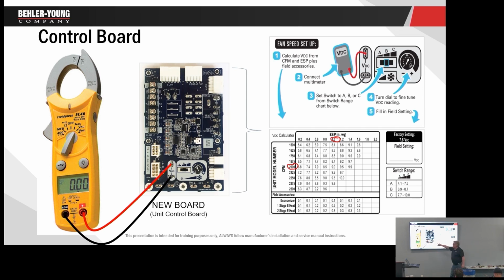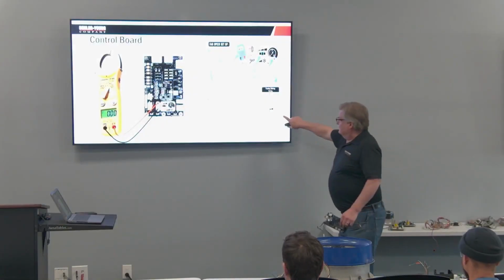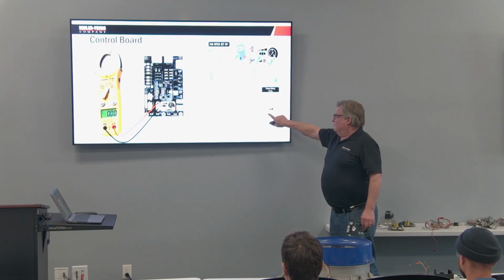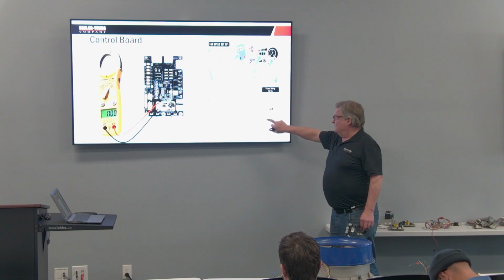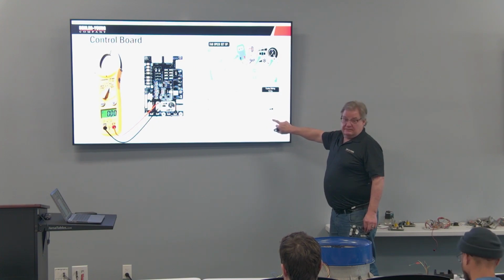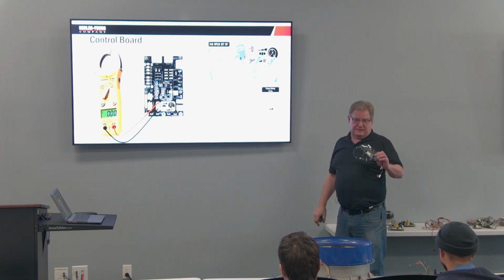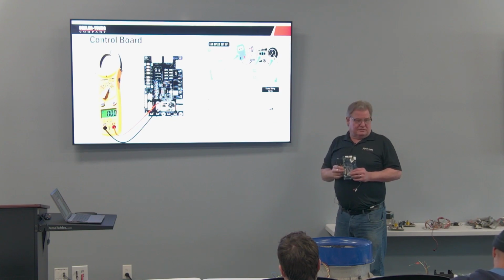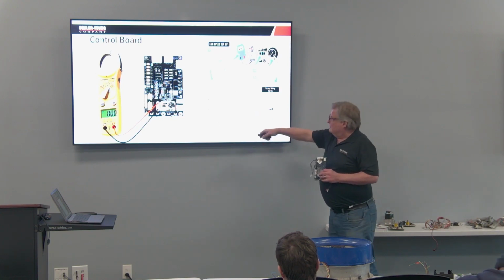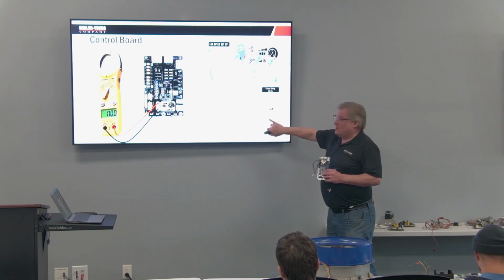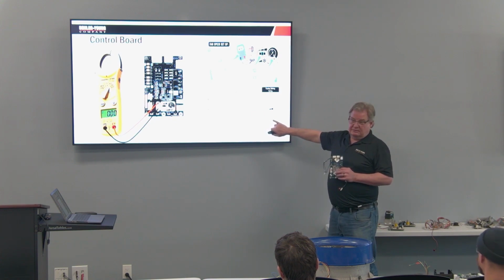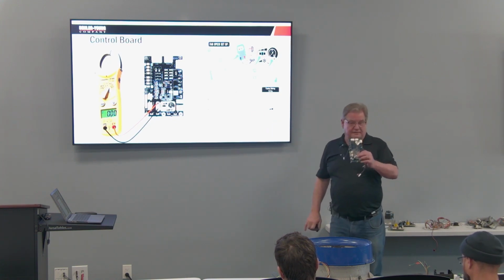There's a switch here that's going to get us into a range, okay? So when I look at this here, I have a switch ABC, it's right here. A is 4.1 to 7.5, B is 6.9 to 8.7, C 7.7 to 10. That's volts DC. So my range is 0 to 10. So I needed 9, so I put the switch at C. All right, so I flip the switch to C.